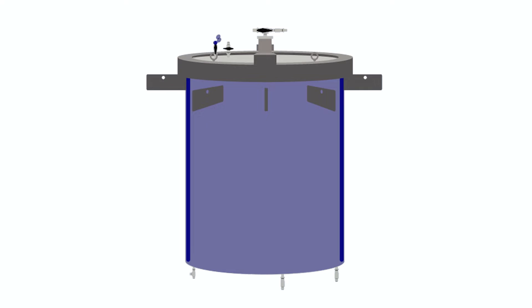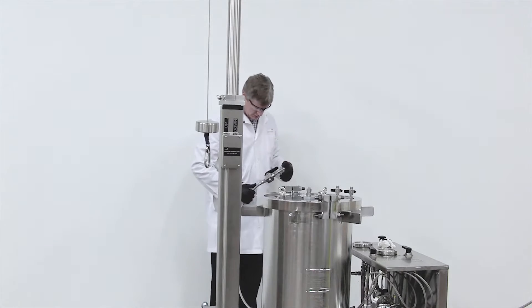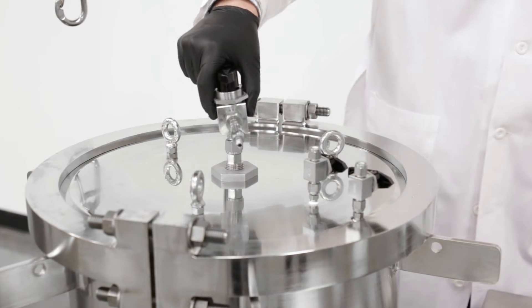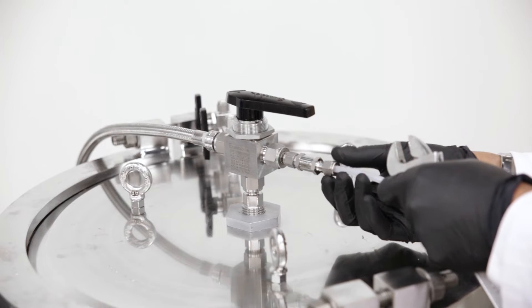When the compression module is isolated, the compressed fluid remains and provides an equal radial pressure around the cartridge. The sample is now loaded via the three-way injection valve mounted on the compression module head.